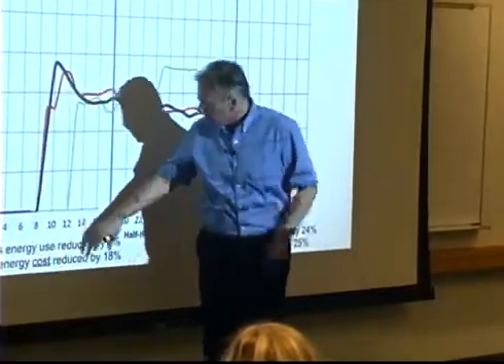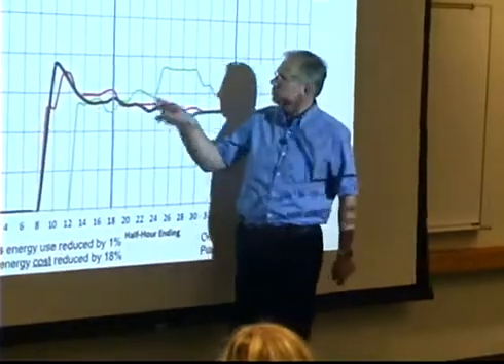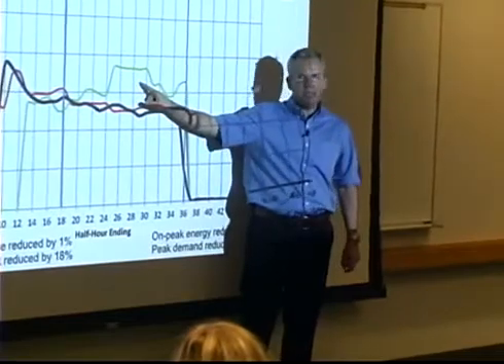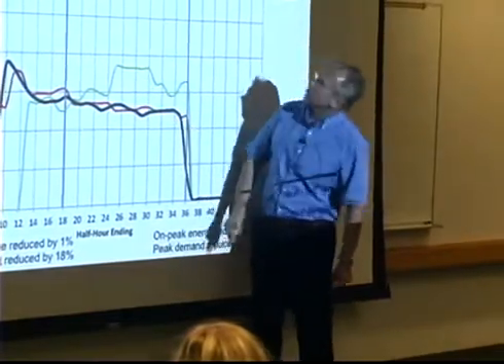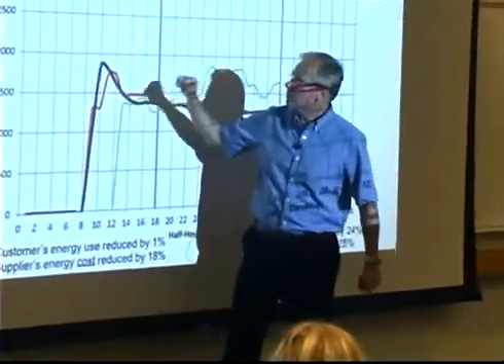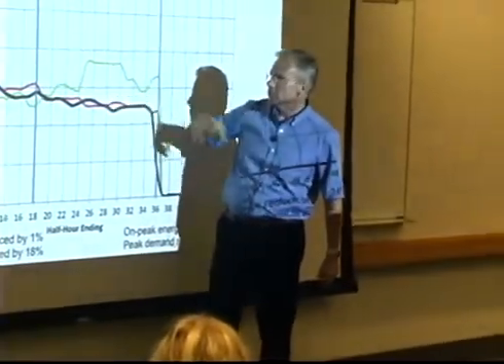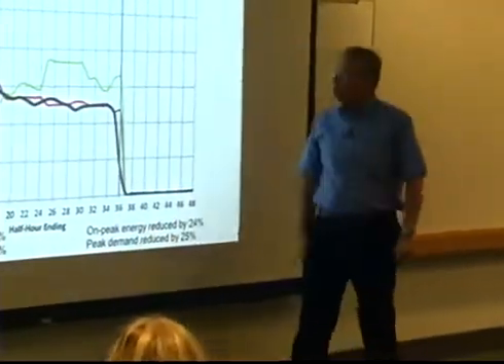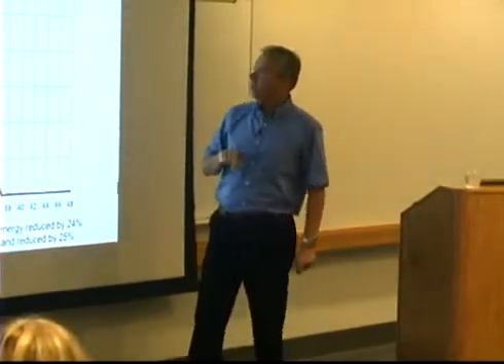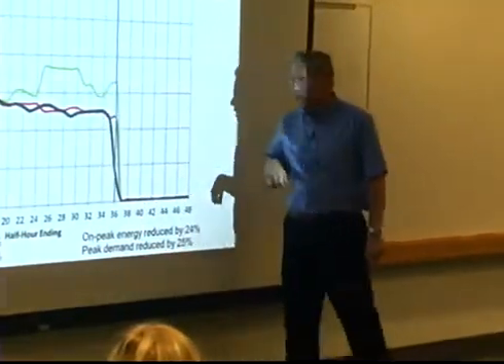The building would have started at 6 a.m. instead of 4 a.m. It would have come up and then would have experienced a very typical afternoon peak in electricity consumption. We see that in many buildings. And if you look closely, you can see that the difference achieved is on the order of, well, that's 1,800 kilowatts down to 1,300, something like that. So we have about 500 kilowatts of demand response achieved during that operation.